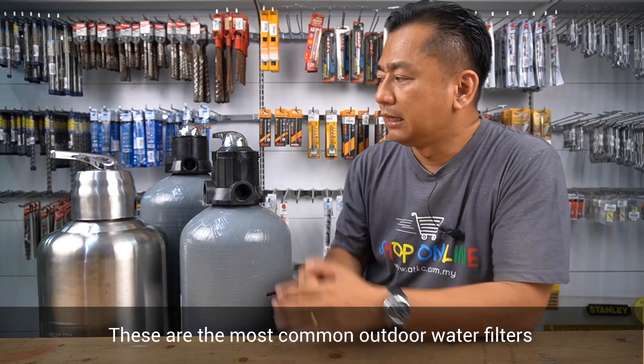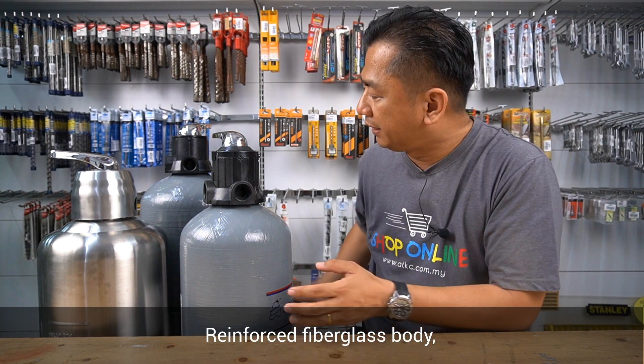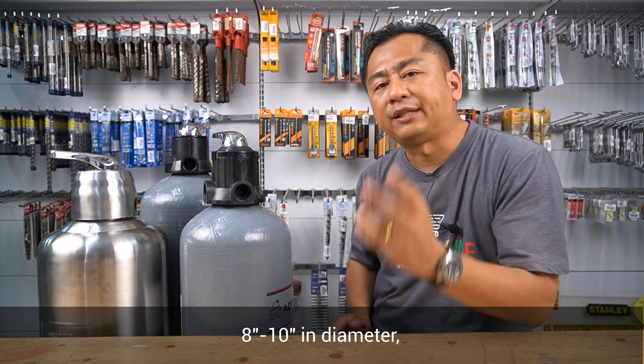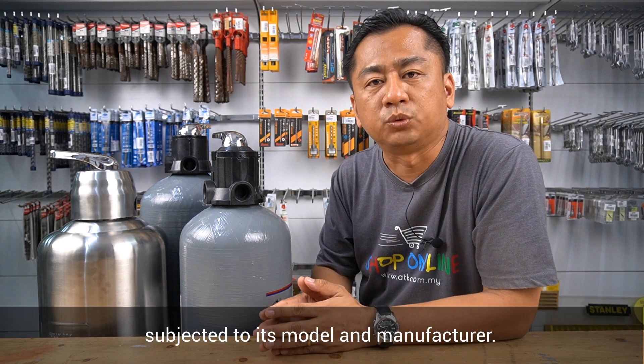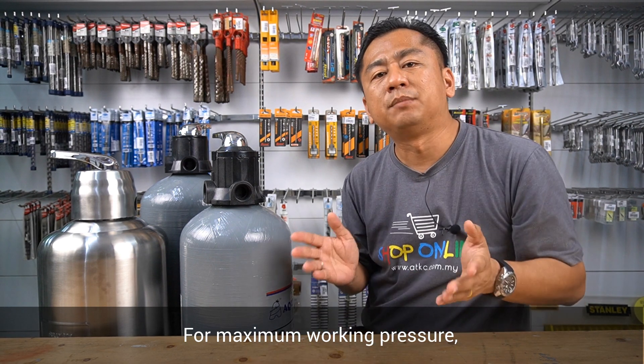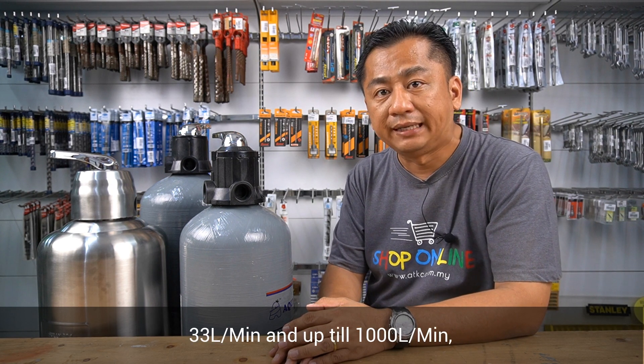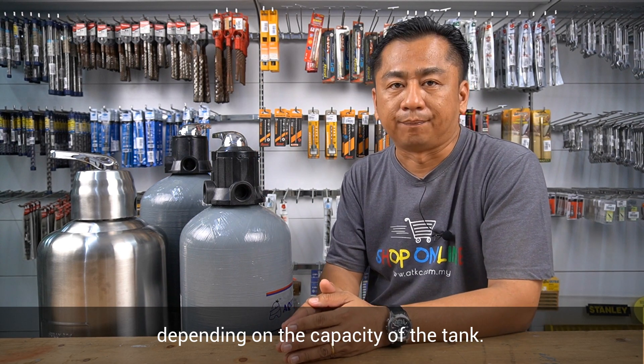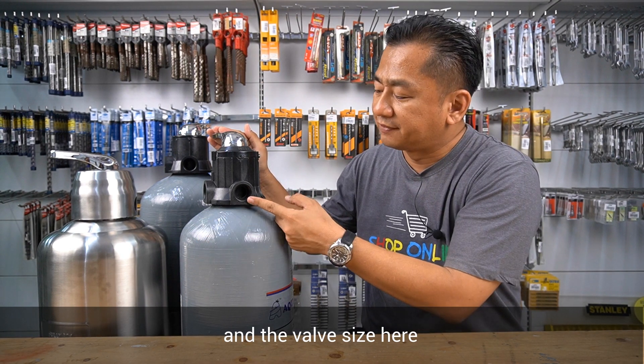Number two: model size and capacity. These are the most common outdoor water filters available in the market — reinforced fiberglass body and stainless steel body. In terms of size, we are looking at 8 to 10 inches in diameter with a height of 44 inches or even more, subjected to its model and manufacturer. For maximum working pressure, it is 120 PSI with a flow rate of 33 liters per minute and up to 1,000 liters per minute depending on the capacity of the tank. This is the multi-port valve MPV, and the valve size here is 3/4 or 1 inch.